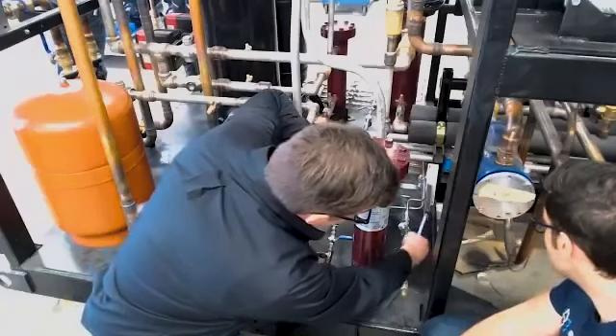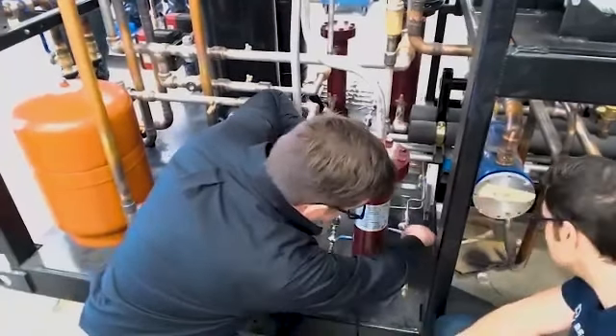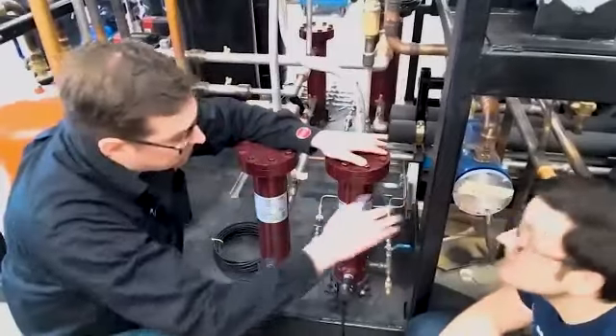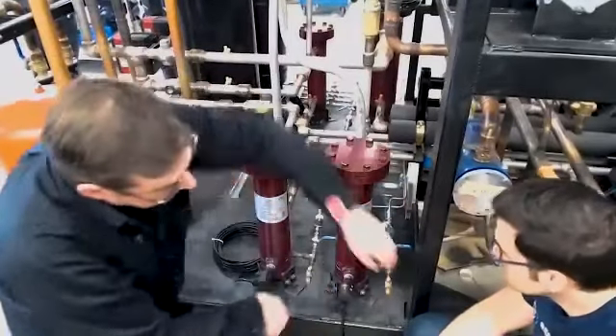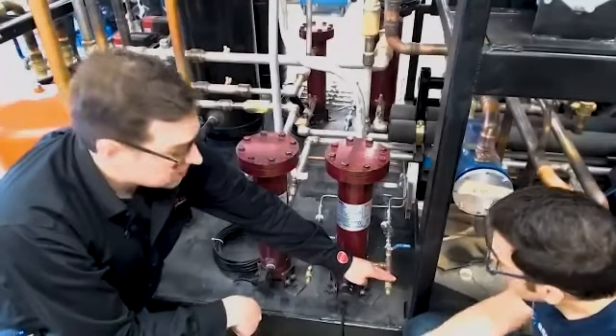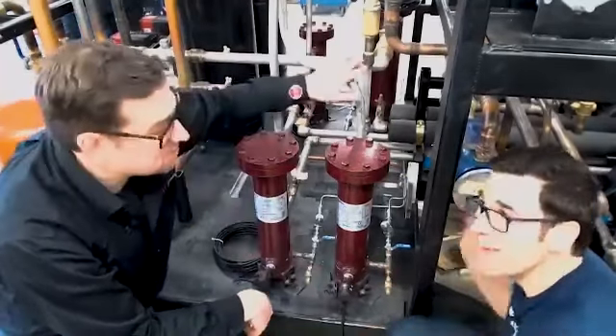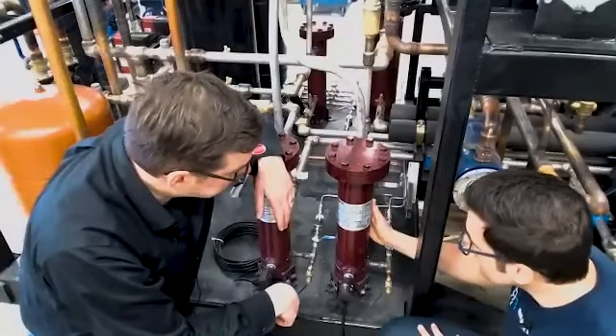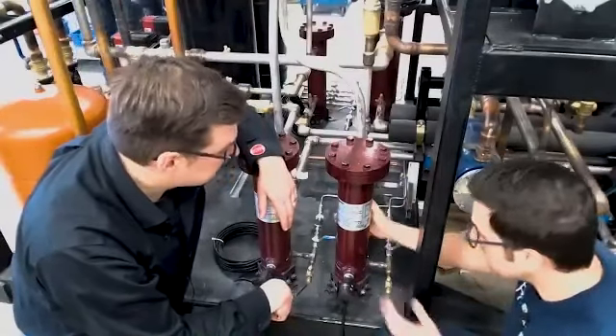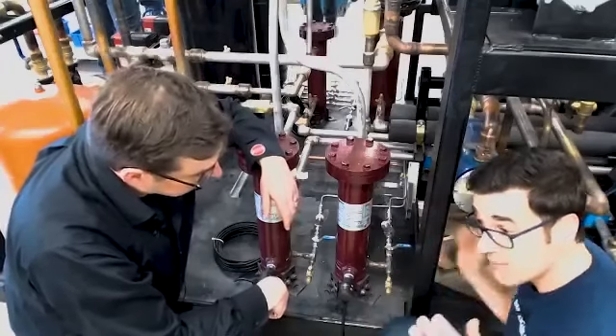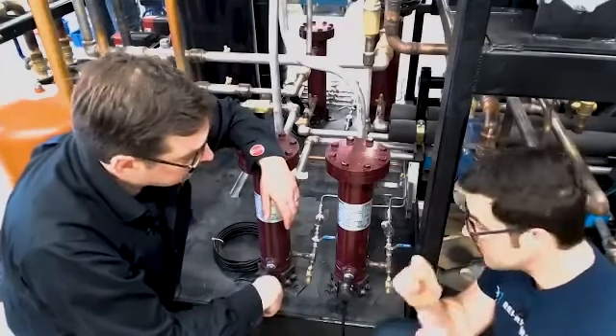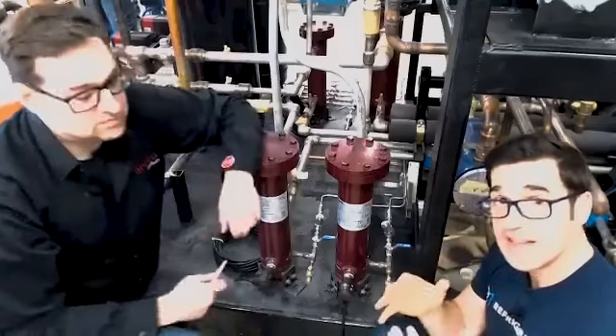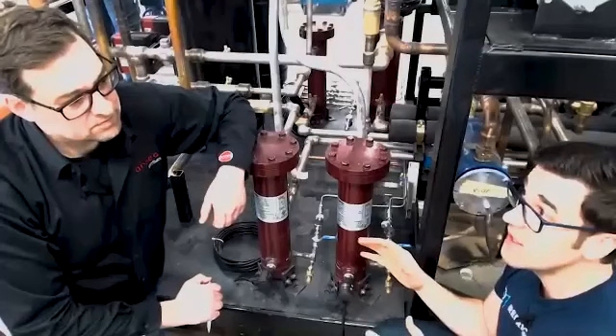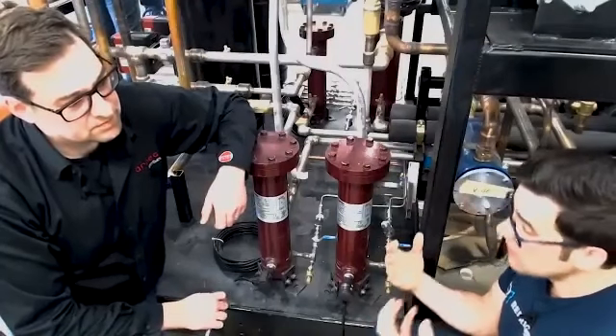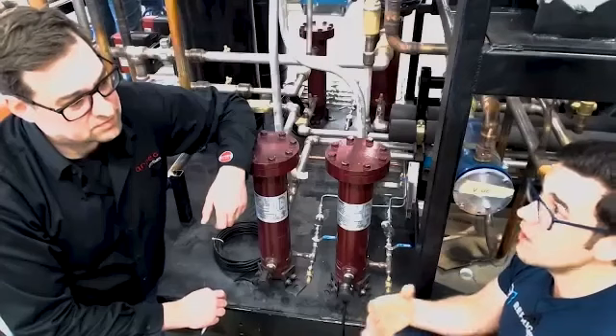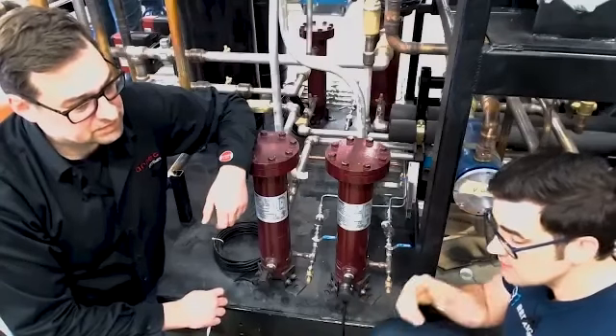Yeah. So this allows, we get a lot of questions for oil tests. You can literally isolate your oil reservoir, turn off your suction group obviously, close it off, and then you got your drain line right here. Relieve some pressure first. Definitely relieve some pressure first, because it could be up to 1200, 1300 PSI. But this is how easy it is to take an oil sample. And oil samples are so important, because you need to be checking the quality of the oil, because I've seen this time and time again. When I used to work at Copeland, a compressor would come back and you would see the copper plating all over. This is POE oil, but it needs to be changed because you can get dirt in it.